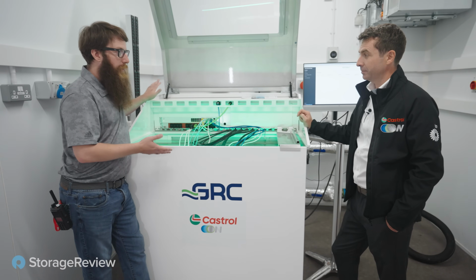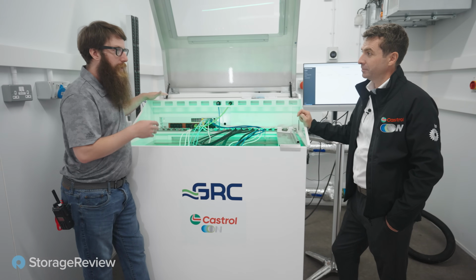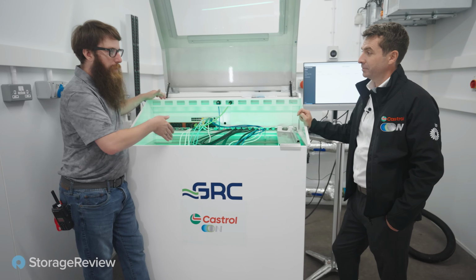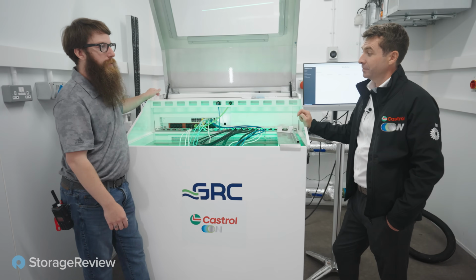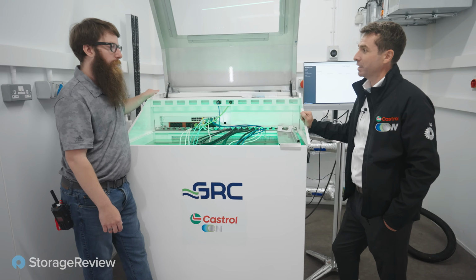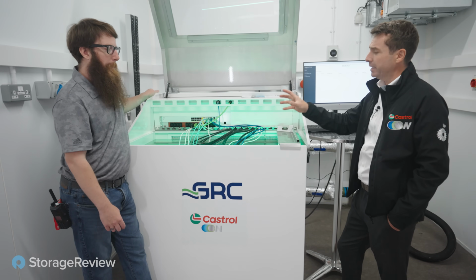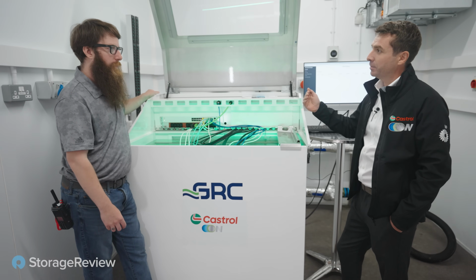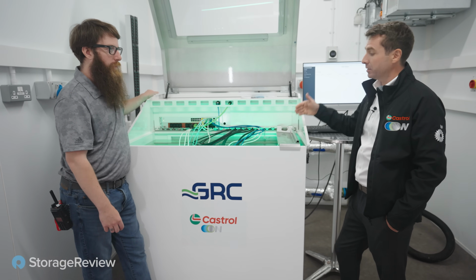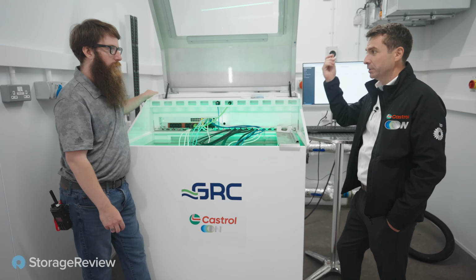So that's an interesting point that you bring up. What changes have to be made to what components in order to be ready to go into an immersion cooling system? Yeah, not too much, it's quite a simple process actually. So what we see is you remove the heat sinks from the CPU and clean the thermal interface material, the paste, away. That's not compatible with immersion cooling, it simply just washes off.